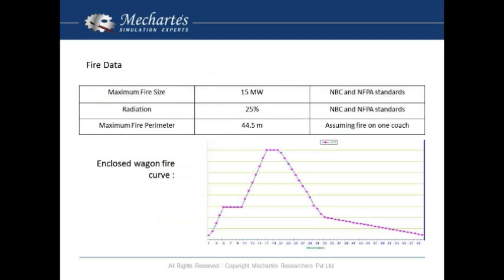For the emergency ventilation system, as per NFPA 130, the design fire was taken from experimental data available through a German paper on enclosed wagon fire curve. It was a 15 megawatt fire peaking, with a flashover at about five minutes, and the peak arrived at around 20 minutes.